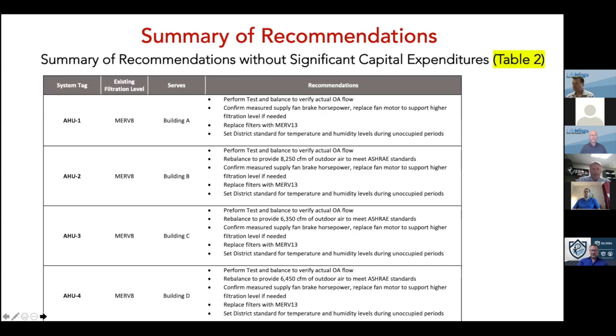The other thing is setting district standards for temperature and humidity levels during unoccupied periods. I know a lot of districts do that as an energy saving measure. But one of the things that we also see is 92 degrees and 60% or 70% RH in a classroom can lead to mold in a quick hurry. So that's also a thing that we should watch for. And we've developed sequences to make sure that we don't go over a certain temperature or a certain RH level, even in unoccupied periods, because it can make a big difference.